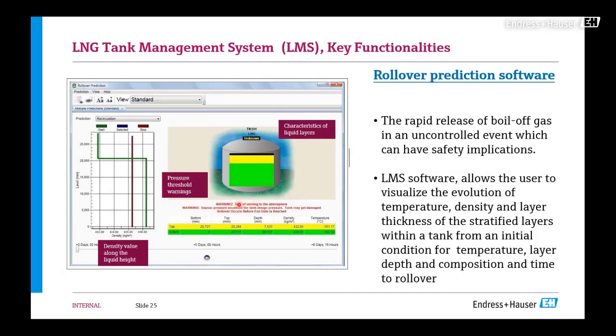Here you can see warning of risk of venting to the atmosphere, warning that vapor pressure exceeded the tank design pressure. As I mentioned, if the predicted rollover may exceed the pressure, you'll have that information on your system, along with the time to rollover. For example, when it runs, it shows you have 6 days plus 15 hours until the rollover happens.